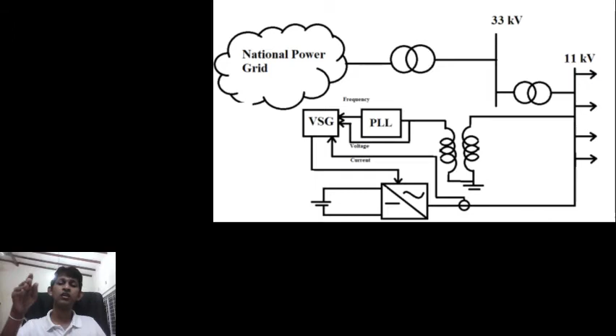But obviously this isn't practical in most cases because we have to install a huge battery energy system storage. Australia Hornsdale power reserve is a classic example for that, developed and maintained and commissioned by Tesla Corporation. But here, what we did was a simulation for a 33 kV feeder from the Ratmalana grid substation. We took a feeder and we manage when the frequency gets down after a certain point, the national grid is taken out and this feeder is being isolated. The frequency is monitored by the PLL and it is being locked, and there is a battery energy system storage to give the power as soon as the national grid is taken out.